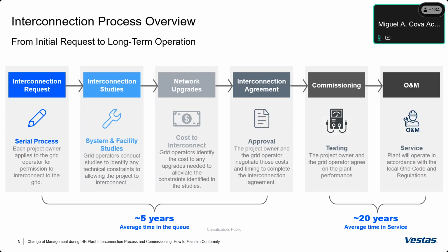But it's foundational that when doing the grid interconnection agreement — and this is the purpose of this slide — the interconnection studies really reflect what we'd like to see. We talked a lot, and the previous presentation focused a lot on the modeling part: how challenging it was to ensure that a user-defined model and its settings, used in an interconnection study, were actually the settings deployed in the field. That's key, and it's only achieved by ensuring the interconnection studies first use a representative model of the product.